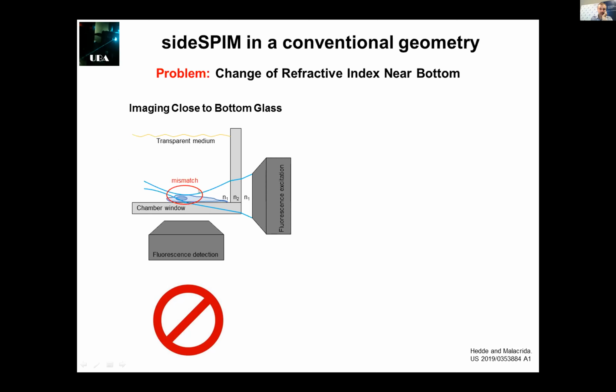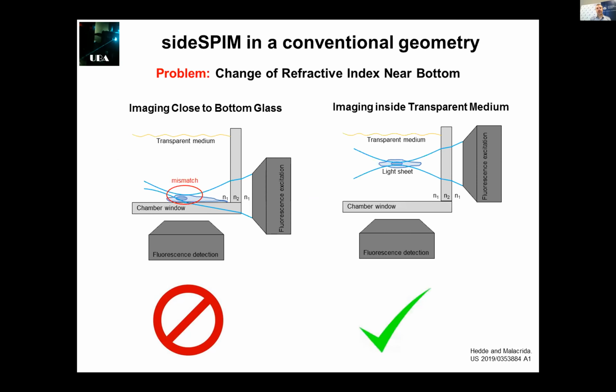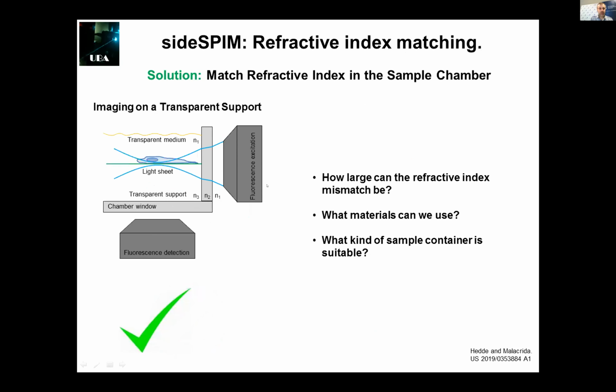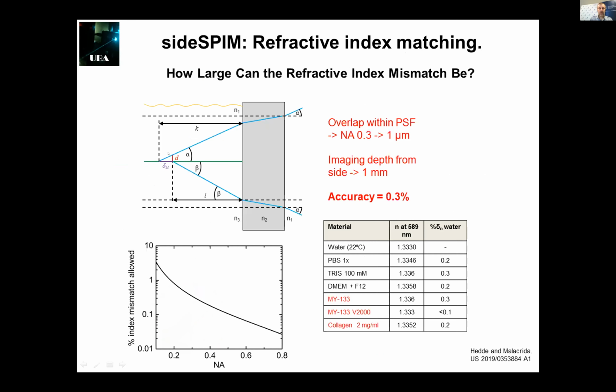And this will distort the formation of the light sheet. So for instance, what we need to do is basically put our sample up in the place where there is no problem with this. So what we found in order to do this was basically we can find some supports that can match the index of refraction of the media where we have our samples. And if we do that, this is solved.